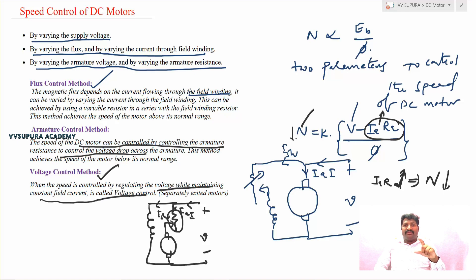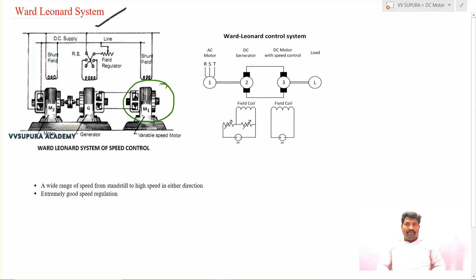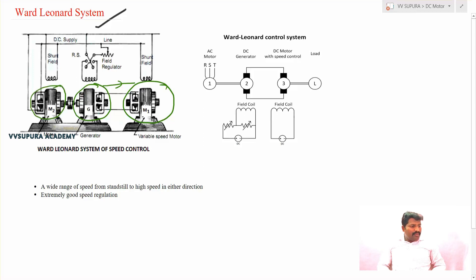In this voltage control method, the field flux or field current is maintained constant, and the supply voltage given to the armature is varied. One implementation is the Ward-Leonard method. In this system, a DC motor whose speed is to be controlled is supplied by a DC generator. To run this generator, another motor is used to provide mechanical energy.